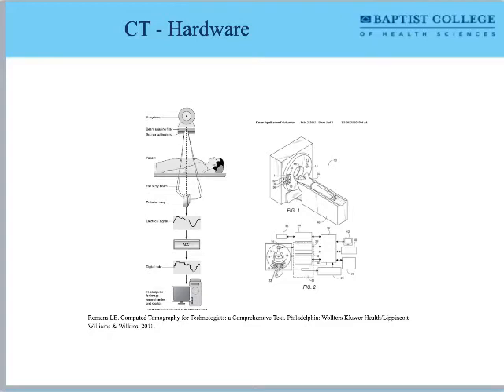Here is the layout of the hardware and how it integrates with software. On the left side we have the x-ray tube; the beam strikes the patient, then strikes the detector, being turned into an analog electrical signal, which is then converted to digital by the ADC. That digital signal is processed by the computer. Pretty much everything from the detector through that conversion is what our textbook calls the DAS — the Data Acquisition System.